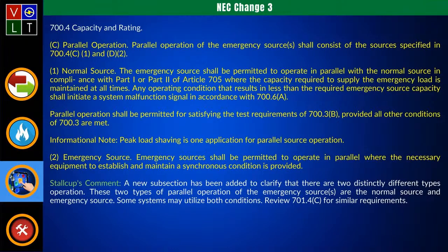Now, another thing they did here dealing with generators, they added a new subsection to help clarify that there are two distinctly different types of operation. You have normal source and you have emergency source. And they want to make sure that you could have some systems that will utilize both of these types of conditions for parallel operations. So you could have normal source and emergency source.